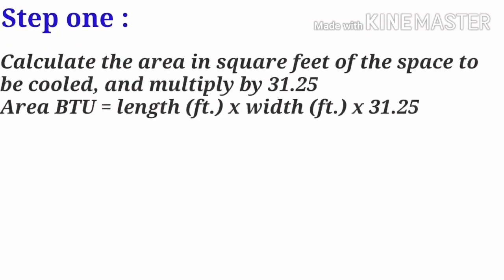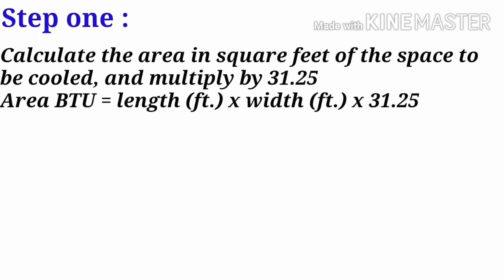Step 1: Calculate the area in square feet of the space to be cooled and multiply by 31.25. Area (BTU) equals length in feet multiplied by width in feet multiplied by 31.25.